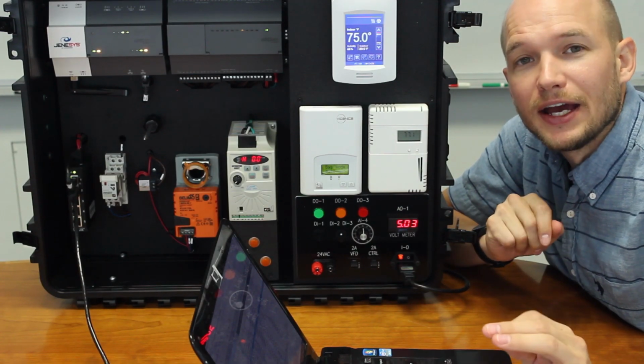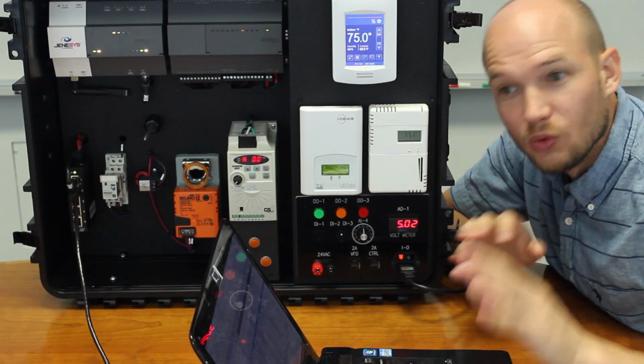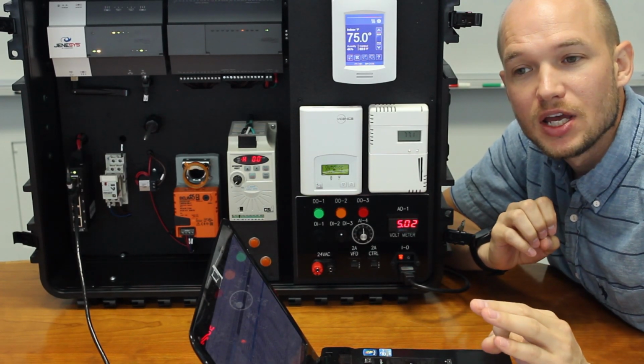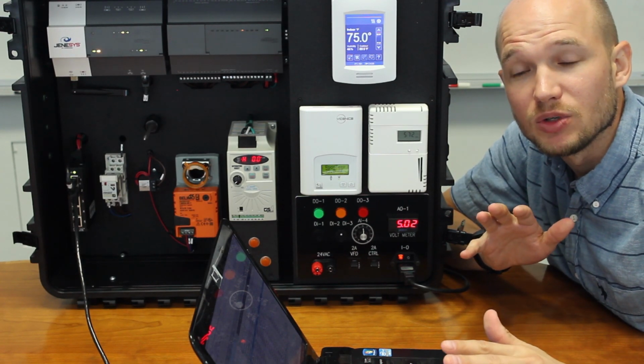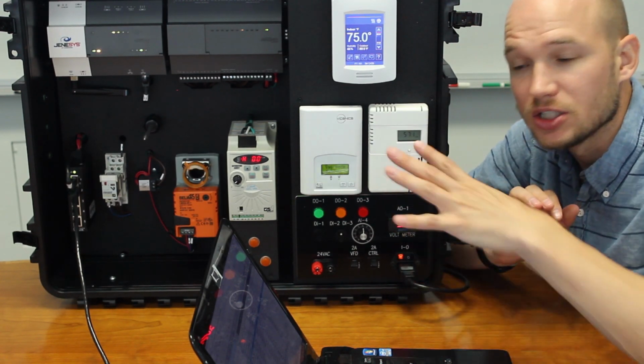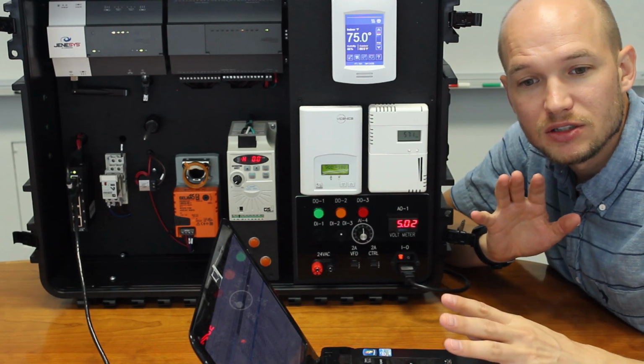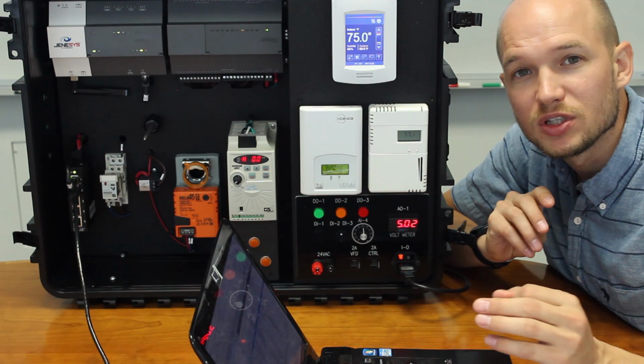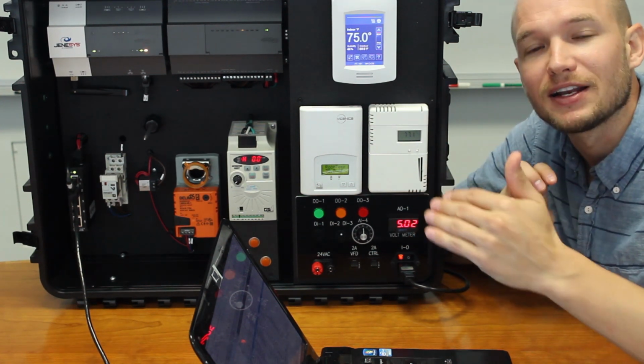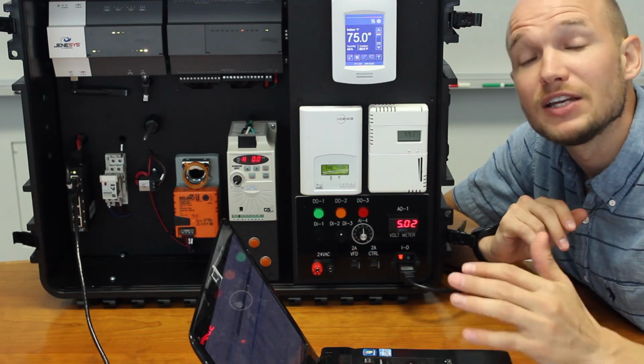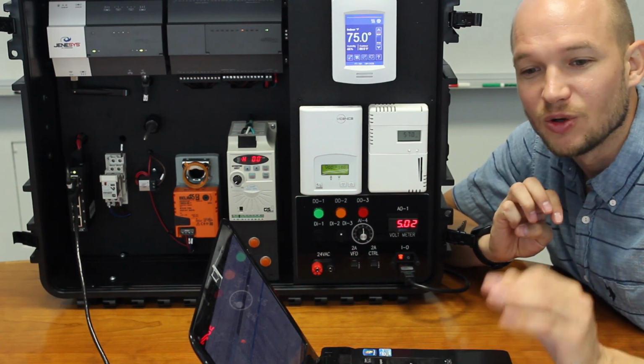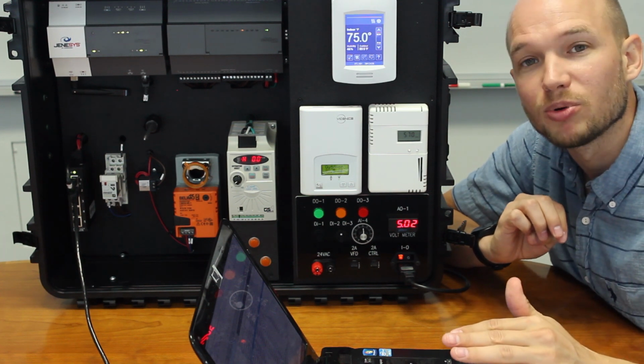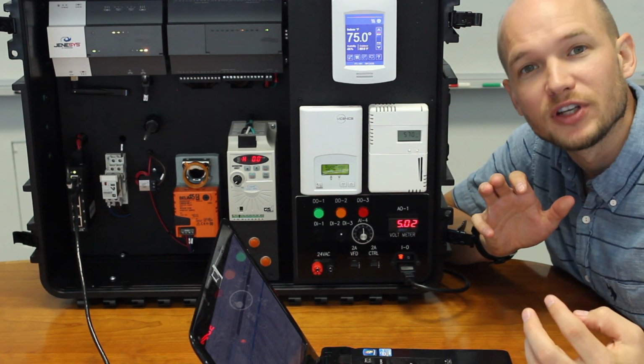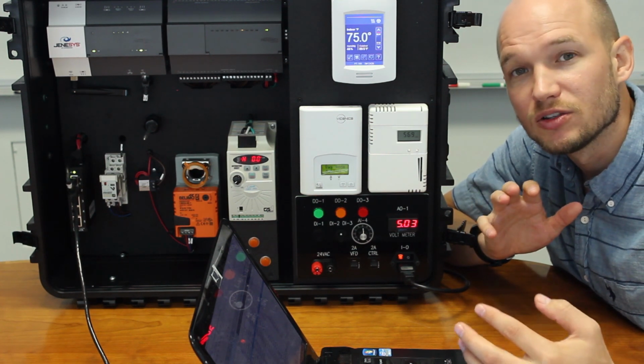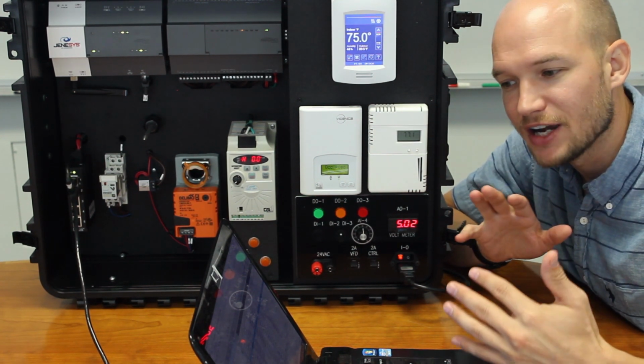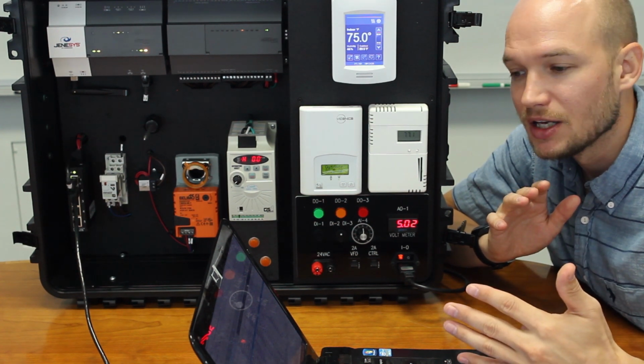And that's not to say that if you go to a facility, it's only going to have BACnet or it's only going to have LonWorks. There are ways to make these systems communicate to each other. So if you're using Tridium Niagara, such as this system, there are conversions or translators that can allow you to speak LonWorks into the controller, to speak BACnet. It may be a different driver that you install. There are ways to do it, right? So don't think that you go to a facility and it's only going to be one protocol. It may be several protocols. You just need to figure out how to get them to communicate to each other. So maybe a translator, it may be a device or a driver. There are several different ways to do it.